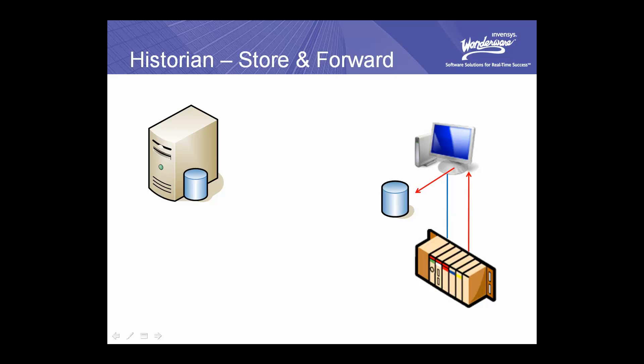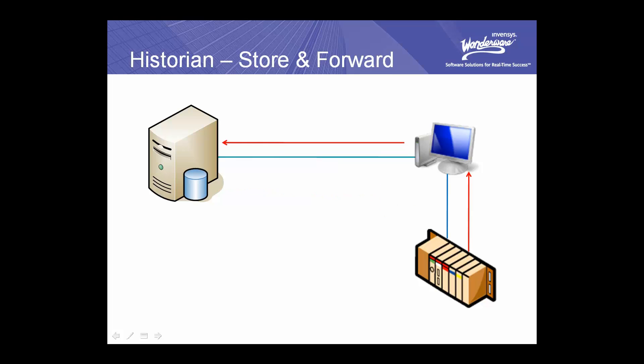But what happens to the data if the remote node can't communicate with the Historian? With Wonderware's Historian, it's cached locally on that remote node until the Historian is available again. When the connection is reestablished, live data as well as the cached data are sent to the Historian for storage. If the server happens to be busy and can't accept the cache data right away, the remote nodes will try, wait a while, and try again until all that data is pushed through. Once it's been forwarded, the local cache is removed. This powerful data logging architecture, which ensures data is not lost, is what we call store and forward.